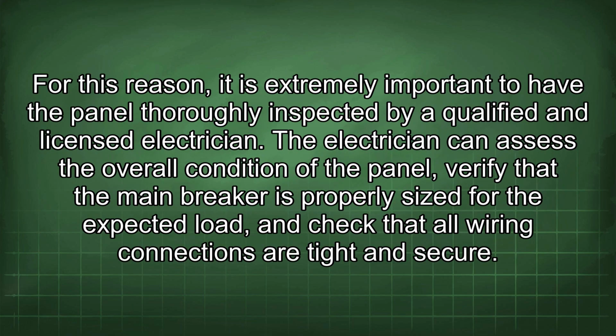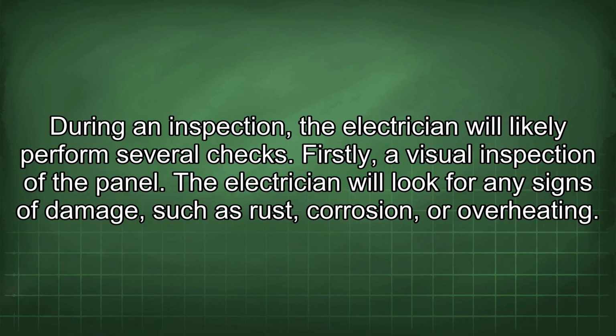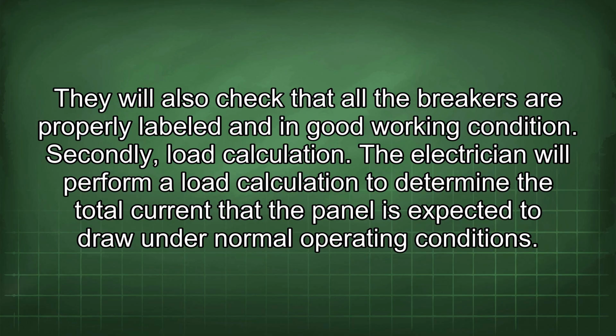For this reason, it is extremely important to have the panel thoroughly inspected by a qualified and licensed electrician. The electrician can assess the overall condition of the panel, verify that the main breaker is properly sized for the expected load, and check that all wiring connections are tight and secure. During an inspection, the electrician will likely perform several checks. Firstly, a visual inspection of the panel. The electrician will look for any signs of damage, such as rust, corrosion, or overheating. They will also check that all the breakers are properly labeled and in good working condition.